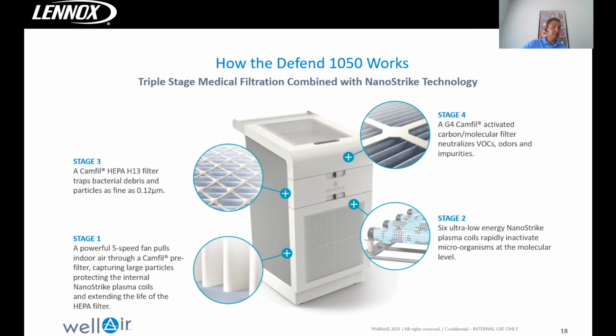The HEPA filter is stage 3, which means that it's not going to be a secondary source of contamination of biohazard like I talked about before, because it's only getting all the dead debris after the virus, the bacteria, the fungi has gone through the Nanostrike tubes. It's getting the debris from all of that stuff going through a plasma tube. It gets captured in that HEPA filter. And then the first filter is just a particulate filter to keep all the impurities out of the unit itself.